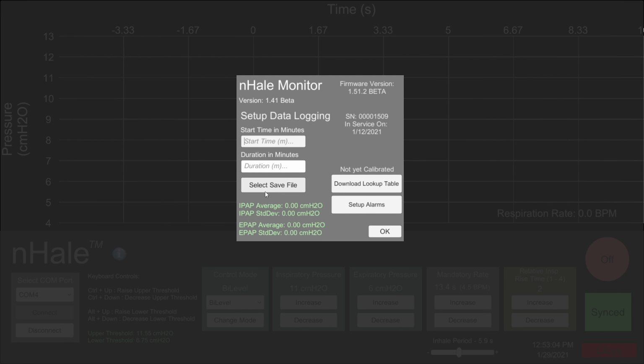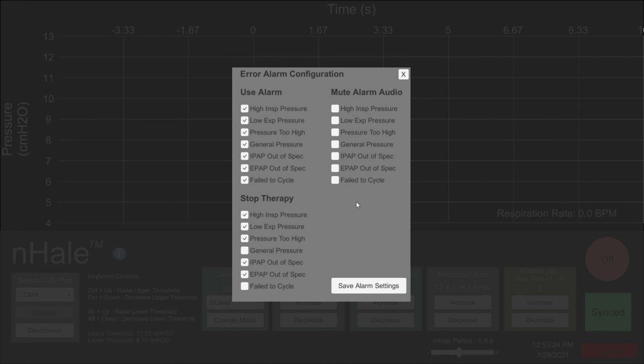To set up data logging, you can enter the start time in minutes and the duration in minutes. Set the location of where the output file should be stored by pressing Select Save File and navigate. To configure the error alarms, press Set Up Alarms. We have flexibility to select which alarms are active and what the response should be by checking and unchecking the appropriate boxes. For example, if we check the low expiration pressure alarm, we can choose to stop therapy or mute the alarm audio if the alarm is triggered.